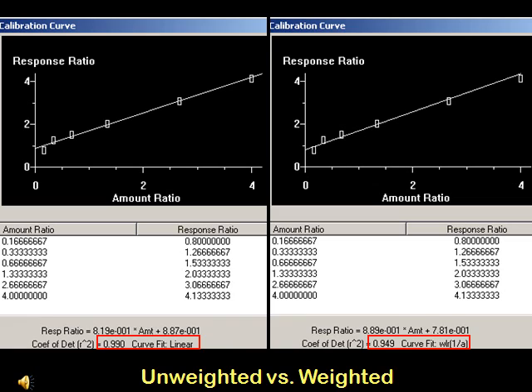In this ADHS example, an unweighted linear calibration model is compared with the same data using a weighted linear calibration model. In this case, the linear unweighted calibration curve actually gives a better r-square value than the weighted curve. In the unweighted curve, the higher linear curve points have more weight and are overwhelming to some extent the effects of the lower calibration point that is askew. In the weighted calibration curve, the lowest askew point has more weight and is having a more overall effect on the curve — this is not always the case. Analysts will need to check on an individual compound basis to see if weighting the curve can help or hurt the accuracy of the resulting quantitation with samples.